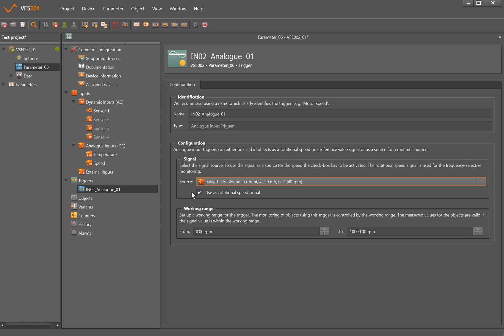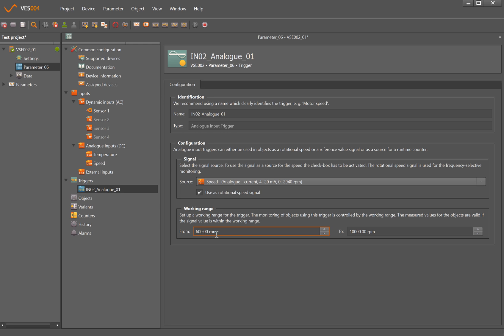The other thing you're allowed to do here as well is set up a working range. So this allows us to not monitor from zero rpm and above, so we can maybe start from say 600, and that allows us to just get past any excess vibrations that are caused by the machine speeding up and slowing down from scratch. And the working range, you can just put the same as the maximum speed of the machine or just a touch higher just in case it gets past that, and at least we're still monitoring the parameters.